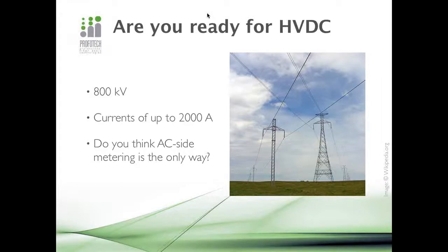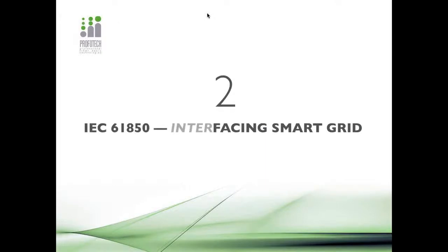Secondly is the HVDC projects deployment. At the moment, the only way to make revenue metering for these HVDC projects is to set the revenue metering on the AC side, because it's high voltage and it has big currents there, so we cannot connect the meter directly, and we can't provide the essential accuracy level. So this is another challenge that we foresee, to organize the DC metering on the high voltage side.